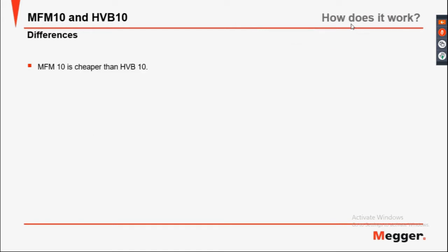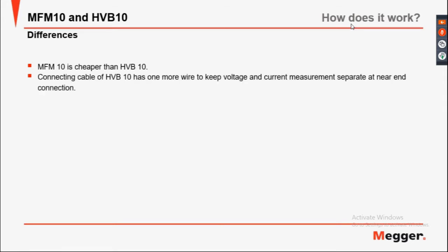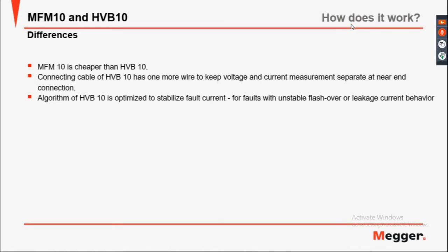Other differences: the MFM10 is cheaper than the HVB. The connection cable of the HVB has one more wire to keep voltage and current measurements separate at near-end connections. The algorithm of the HVB10 is optimised for stabilize fault current — faults with unstable flashover or leakage current behaviour.